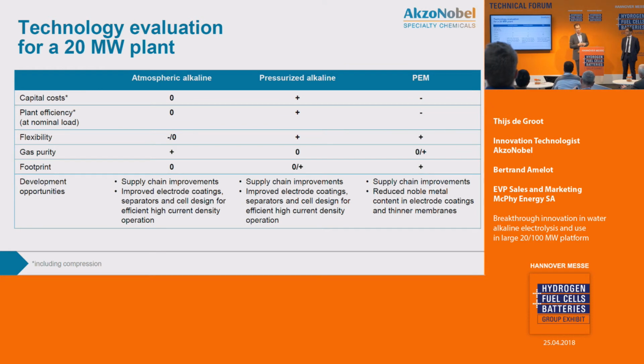PEM suppliers often argue that their flexibility is better. What we learned is that flexibility is mostly an issue of transformers and rectifiers. With the right transformers and rectifiers, you can be very flexible. That doesn't fully apply to atmospheric alkaline because of gas volumes, but for pressurized alkaline you can get flexibility in the order of 10 to 30 seconds, which is sufficient for grid services. So there's no real difference there.